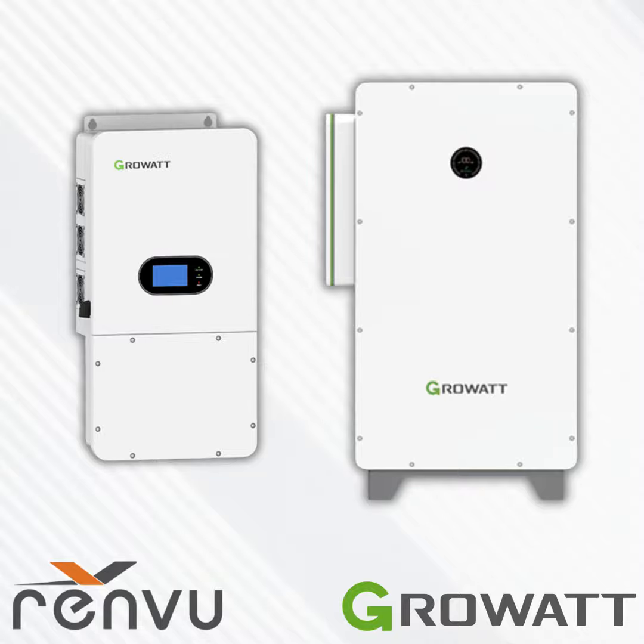So our SPH 10,000 TLHU-US is relatively new to the US. It was officially CEC listed in June. So we have been selling and installing them for a few months now in the US. And ourselves and a number of customers have been really excited about this product. So it can support up to 15,000 watts PV power. And it has three MPP trackers, which can each support two strings up to 22 amps. Nominal AC output power is 10,000 watts. Max output current is 50 amps.